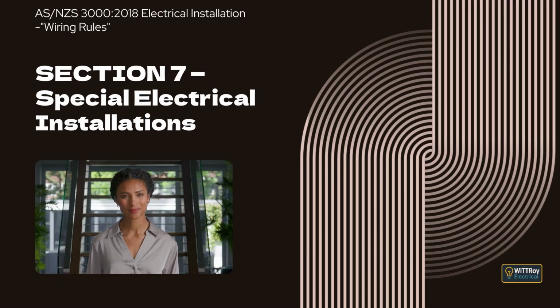Where no wiring system classification is specified, the wiring must be capable of maintaining supply when exposed to fire or mechanical damage, or must maintain supply when exposed to fire while being protected against mechanical damage, either by effective enclosure or by suitable location. It also explains that these protection requirements do not apply where wiring is already installed in a protected enclosure or location, or for circuits supplying lifts beyond the terminals of a circuit breaker in the lift machine room used for control and protection of the lift installation.